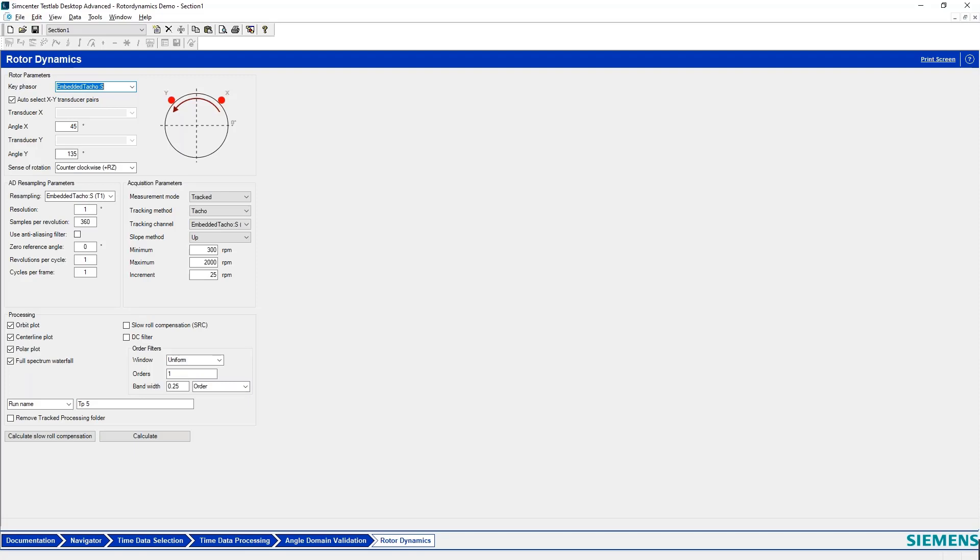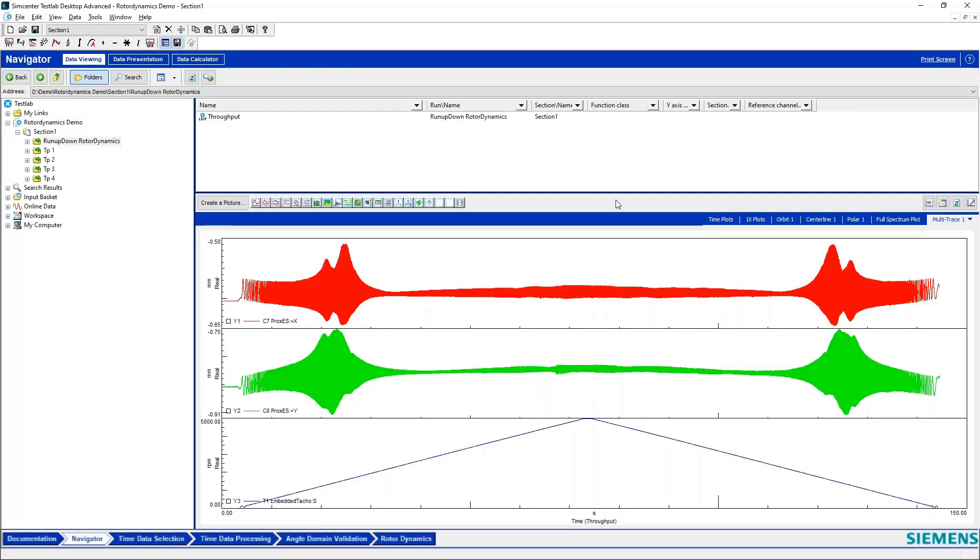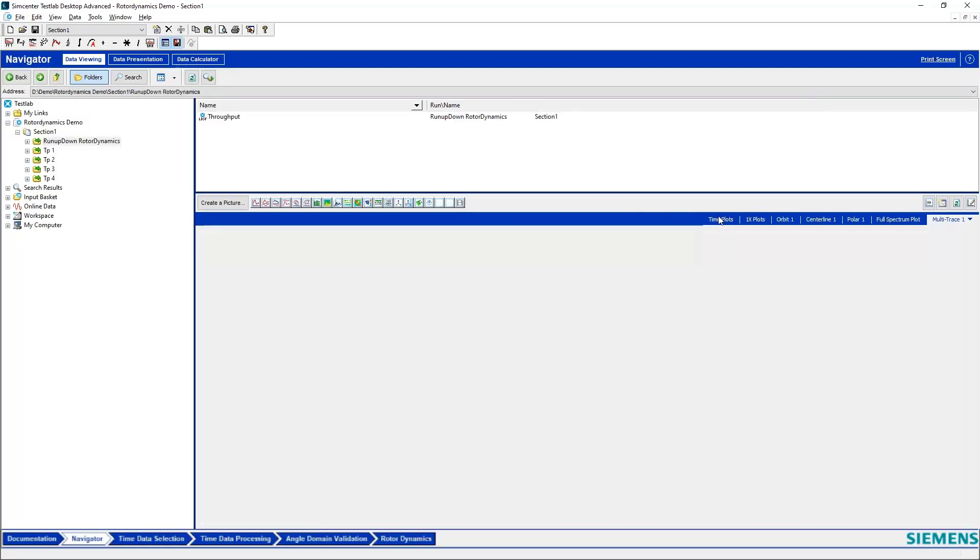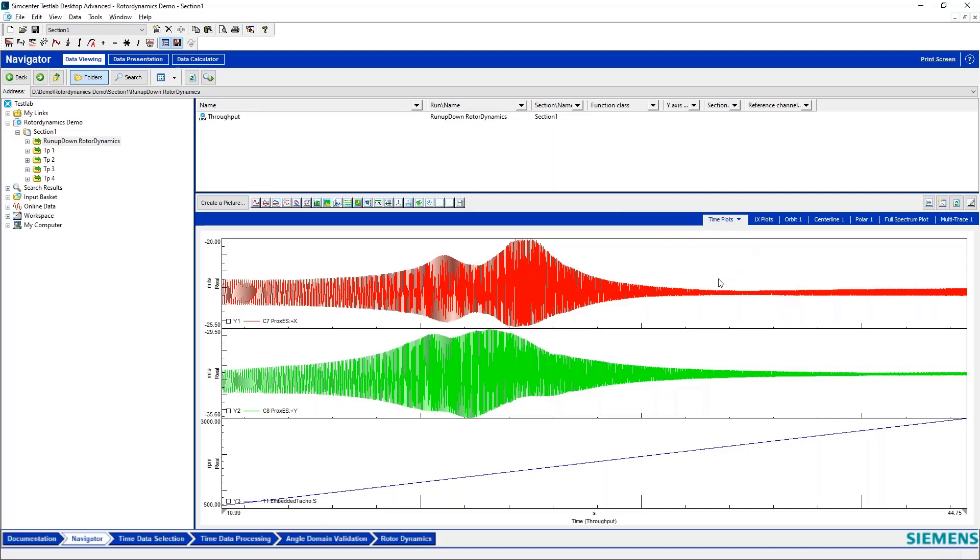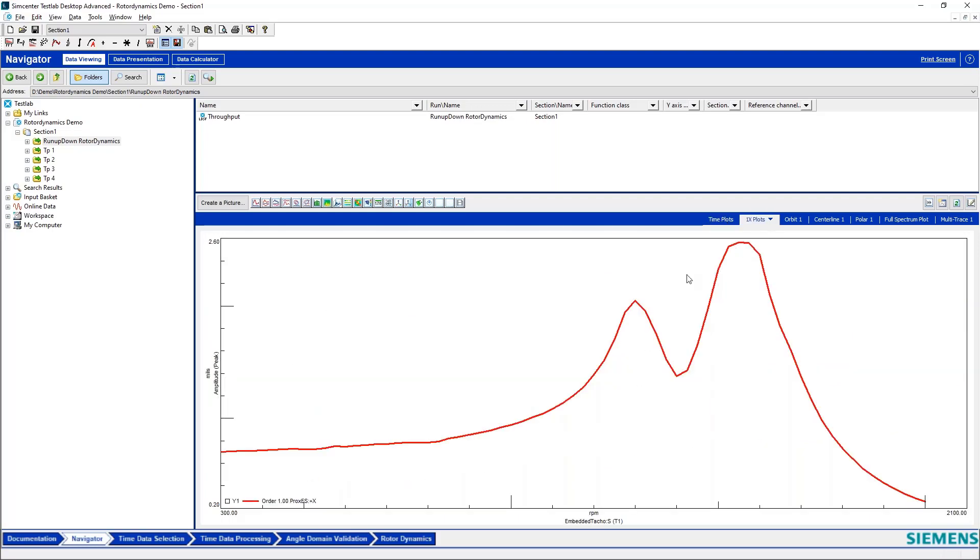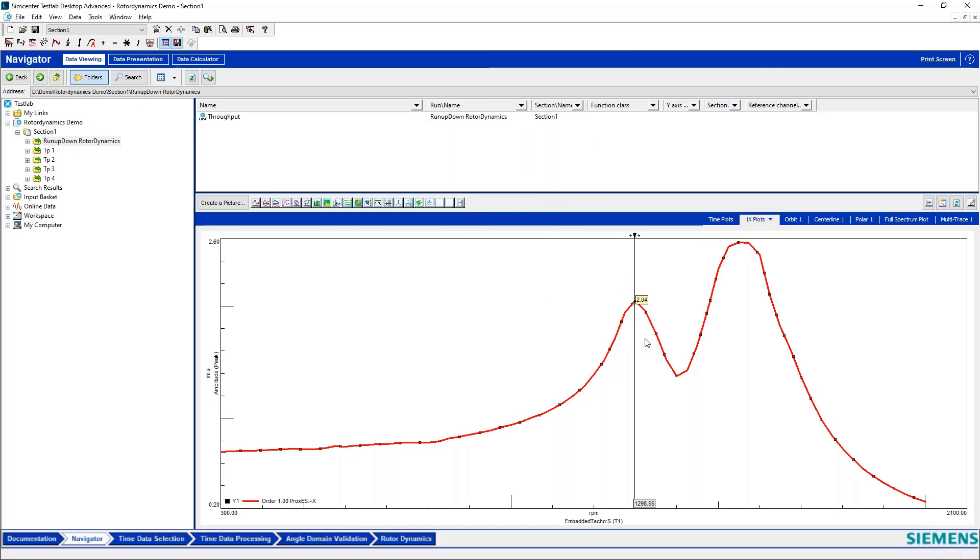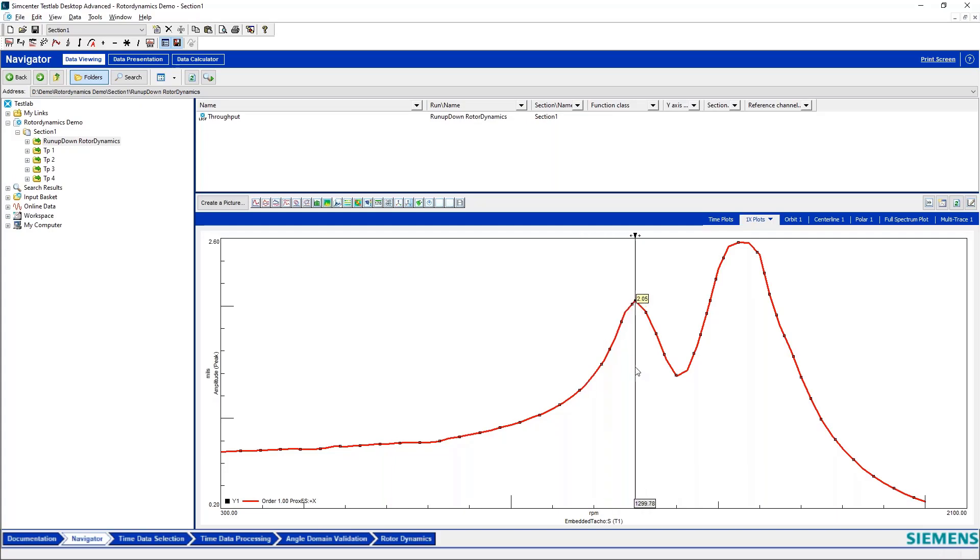I will hop now back over to navigator and we can talk about a couple of these plots. Like before I mentioned our time-based plots, here we can just see the vibration amplitudes of my two different proximity probes, my rotational speed. I can also show this as a Bode plot, although here normally you would show the phase, where I have filtered this vibration data that's just showing only vibration data at one times the rotating speed of the machine. And it looks here like I have two different shaft resonances. So I've got a peak here at 1300 RPM and a peak here at 1550 RPM or so. That's an indicator that I might have two resonances at these particular speeds.